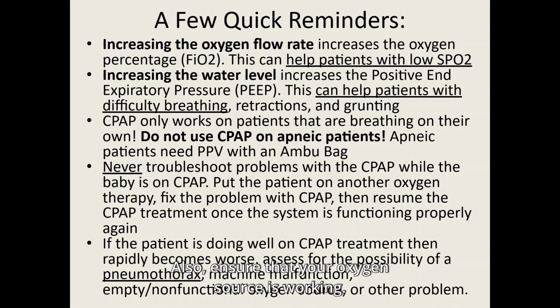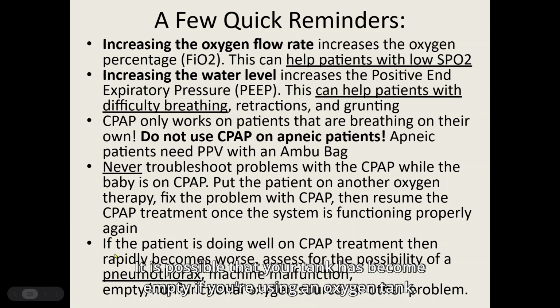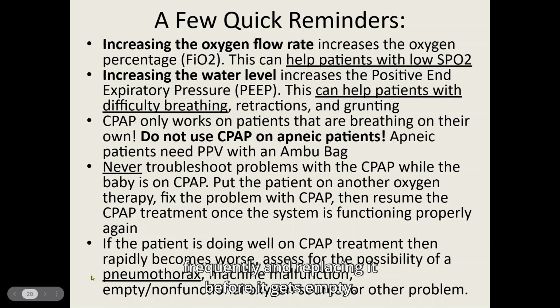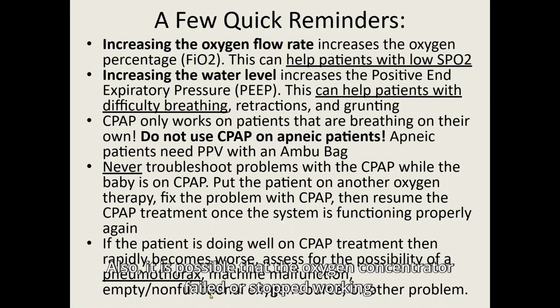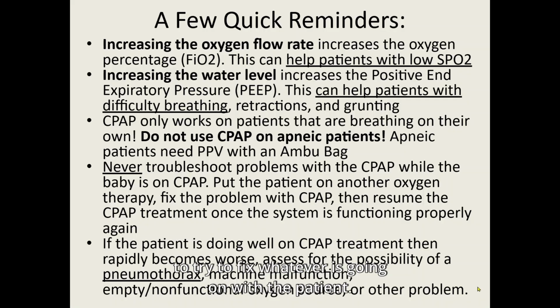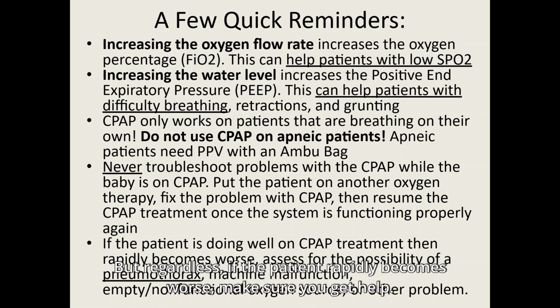Also, ensure that your oxygen source is working. It is possible that your tank has become empty if you're using an oxygen tank. Hopefully not, because you are checking it frequently and replacing it before it gets empty. But if something happened and the tank became empty, that could be a source of the problem. Also, it is possible that the oxygen concentrator failed or stopped working, so make sure you check your oxygen source and continue to assess anything else that might be a problem to try to fix whatever's going on with the patient. Obviously, if the patient rapidly becomes worse, this is an emergency, especially if it is a pneumothorax. But regardless, if the patient rapidly becomes worse, make sure you get help. Call the doctor immediately. Get help.